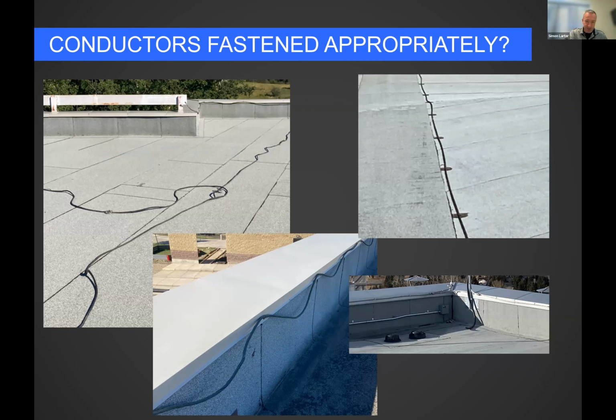Roofer specials again, folks. They pulled the lightning protection up and put it back the way it was. That doesn't look like the way it was. The cable is just coiled up on the roof. It snakes all over there. There are no fastenings. The reason we fasten our conductor is there are some significant electromechanical effects.